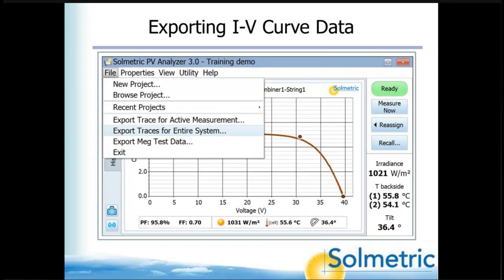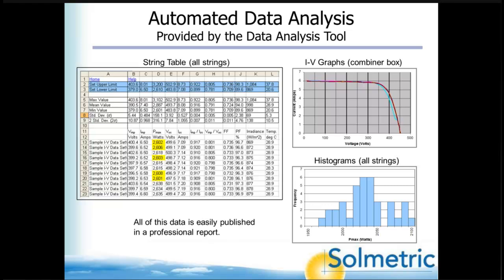You export your data by going to File, Export Traces for entire system, and then analyze that data with the data analysis tool. It produces three types of displays: a string table for all your string measurements, the main parameter values, the statistical summary at the top, and even some limit checking.